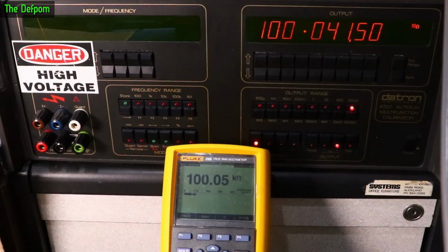I could change the camera so you can see both, but I'll just tell you what they are. This is 100k, which is 4 counts high on the meter here because it's 100.0028. 10k is 5 counts high as per my Datron calibrator here. This is just confirming the Datron is doing the same thing. This is saying 3 counts high, so it's 1.000253.